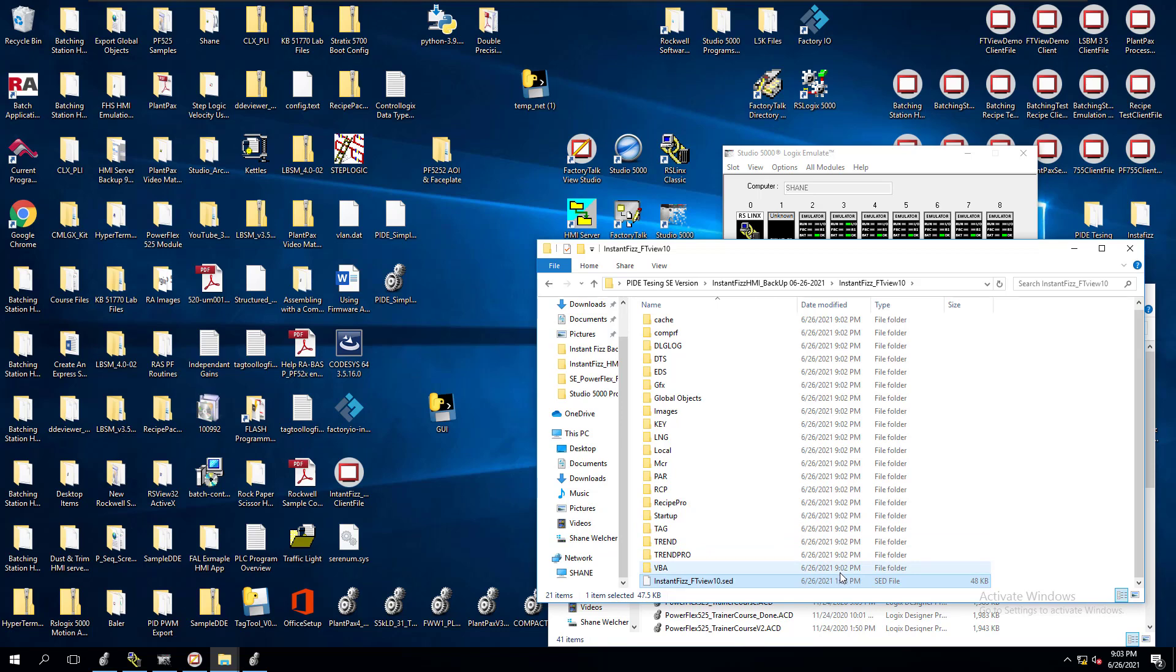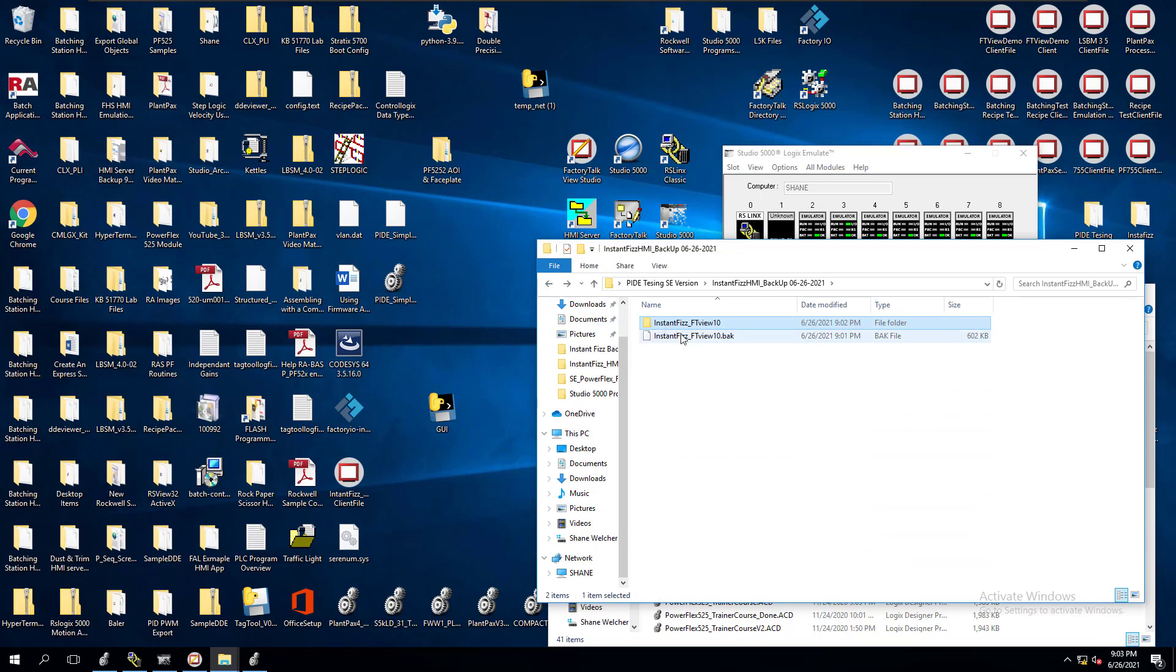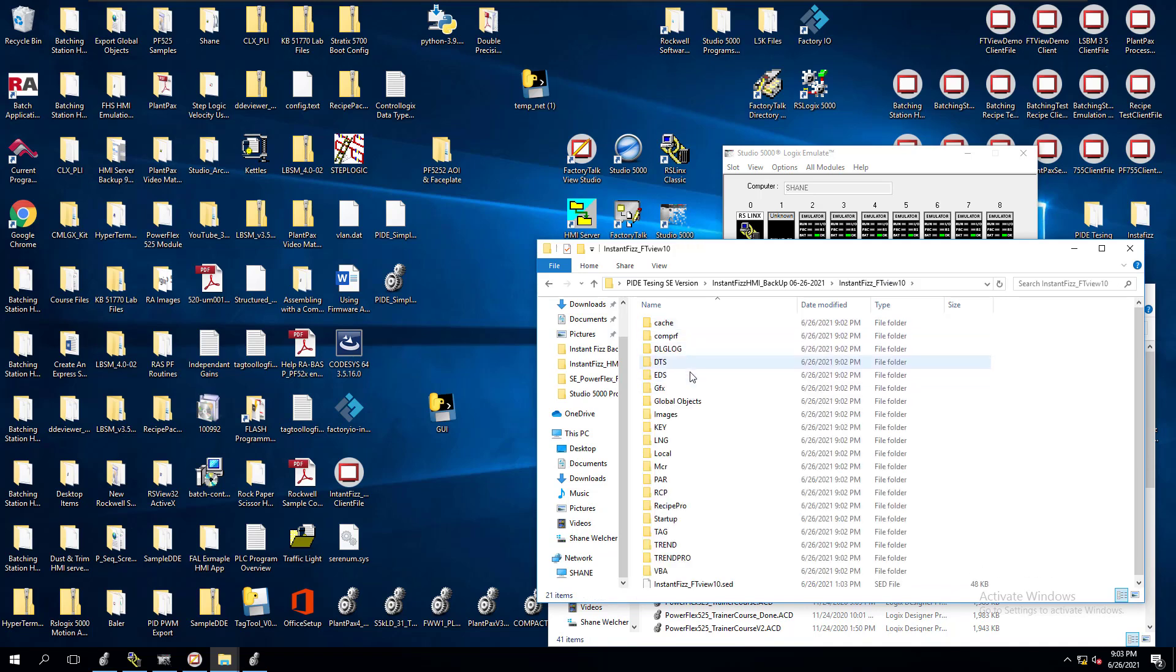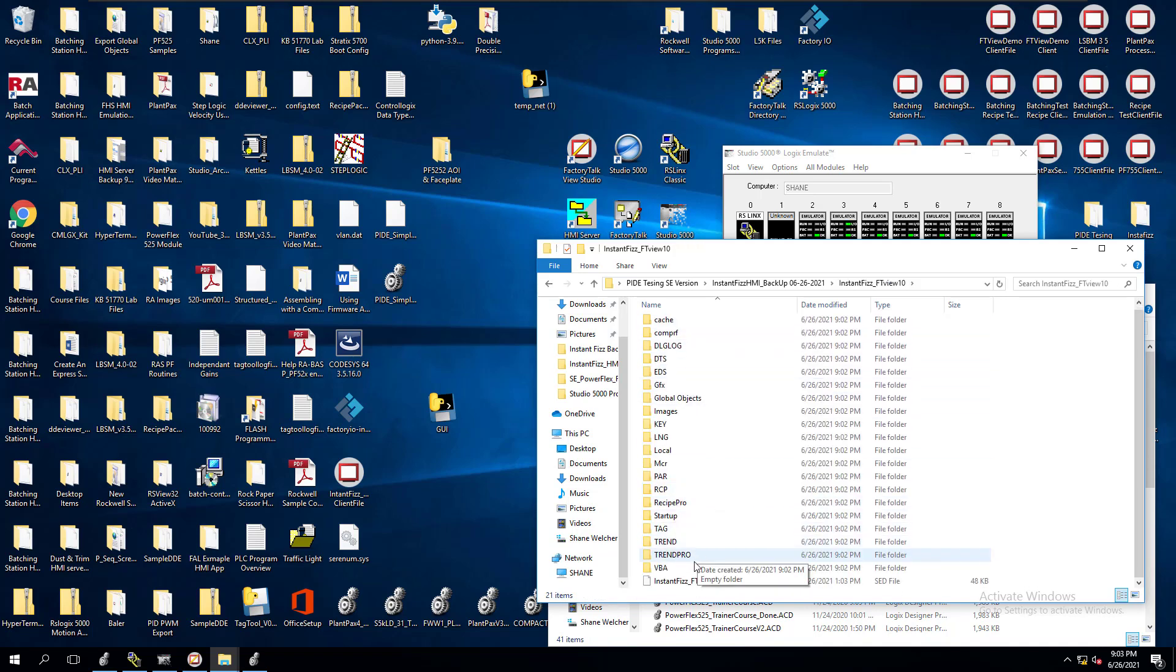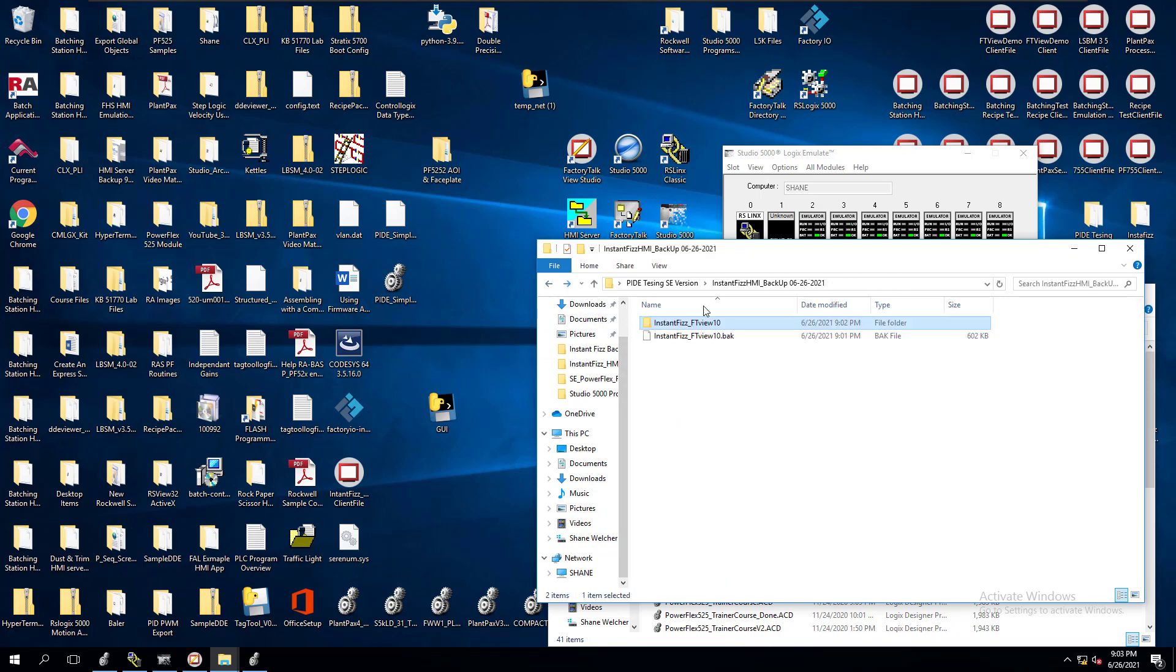Go ahead and do the restore on another computer to make sure it's good. But I would definitely double check it if it is 103 kilobytes. Coming back to this, these are the two files that we need. We need the BAK file, which is our admin backup, and then we need the FactoryTalk application itself. So we're going to utilize both of these, and that's our full backup.